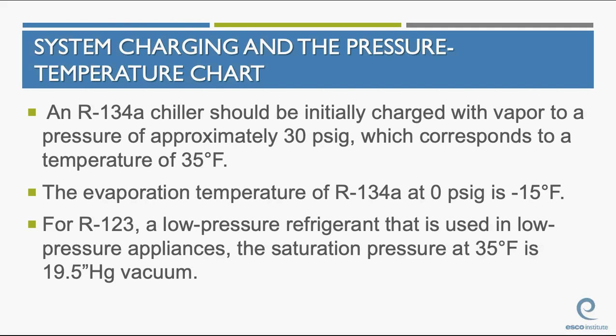For R123, it's a low pressure refrigerant that's used in low pressure appliances. Again, now we're talking low pressure. The evaporator runs under atmospheric pressure. 35 degrees is approximately 19.5 inches of vacuum. Okay, does everybody see the difference right here? We've sort of drawn a line. Low pressure appliances, the evaporator runs under atmospheric pressure. It's a very important distinction. The saturation pressure of R123 at 35 degrees is about 19.5 inches of mercury. Does anybody have a question on that?